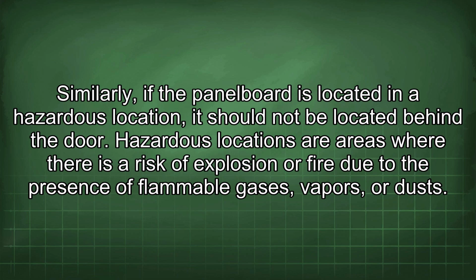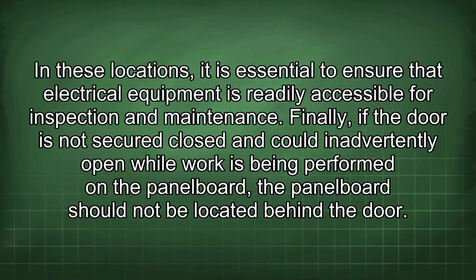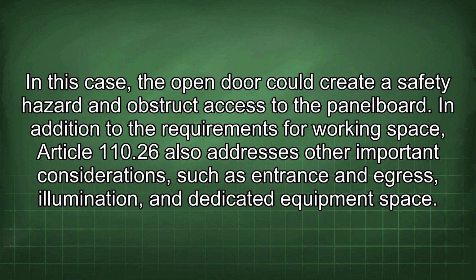Similarly, if the panel board is located in a hazardous location, it should not be located behind the door. Hazardous locations are areas where there is a risk of explosion or fire due to the presence of flammable gases, vapors, or dusts. In these locations, it is essential to ensure that electrical equipment is readily accessible for inspection and maintenance. Finally, if the door is not secured closed and could inadvertently open while work is being performed on the panel board, it should not be located behind the door. In this case, the open door could create a safety hazard and obstruct access to the panel board.